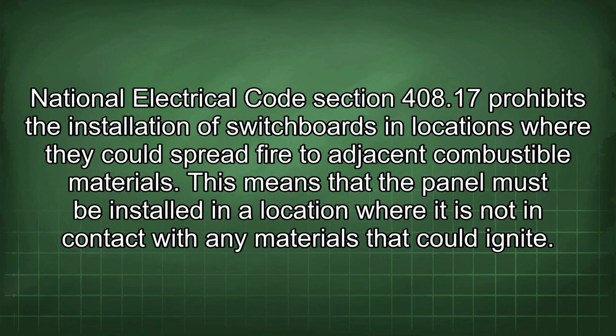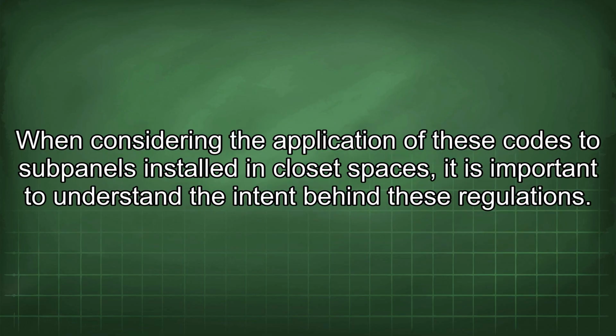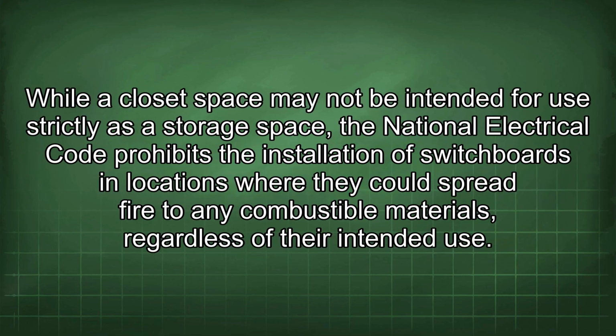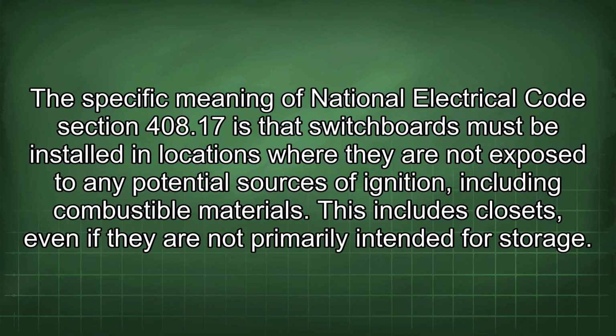materials that could ignite. When considering the application of these codes to subpanels installed in closet spaces, it is important to understand the intent behind these regulations. While a closet space may not be intended for use strictly as a storage space, the National Electrical Code prohibits the installation of switchboards in locations where they could spread fire to any combustible materials, regardless of their intended use. The specific meaning of National Electrical Code Section 408.17 is that switchboards must be installed in locations where they are not exposed to any potential sources of ignition, including combustible materials. This includes closets, even if they are not primarily intended for storage.